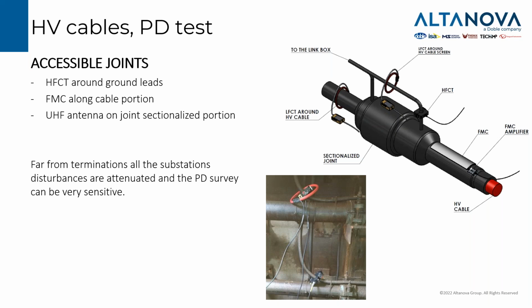A key point that is a very big help for the testing engineers when testing high voltage joints is that normally the joints, especially for long circuits, are far away from the termination of the cable. And the terminations of the cable are the only places where we have external disturbances entering our measuring chain. So we expect a very good signal to noise ratio in the joints, and we do not have to fight against external signals and disturbances.